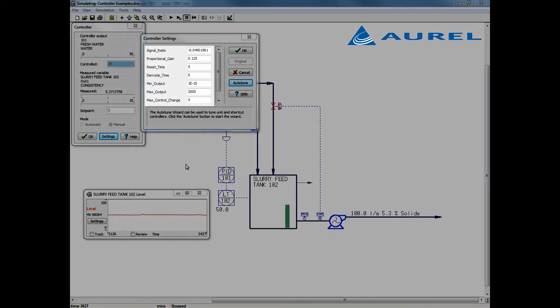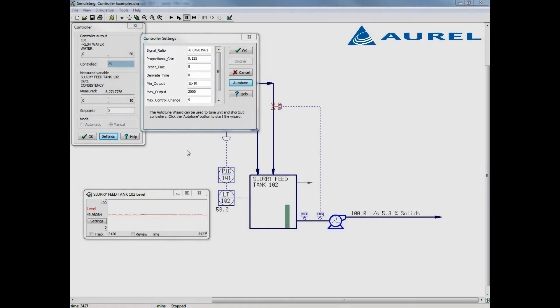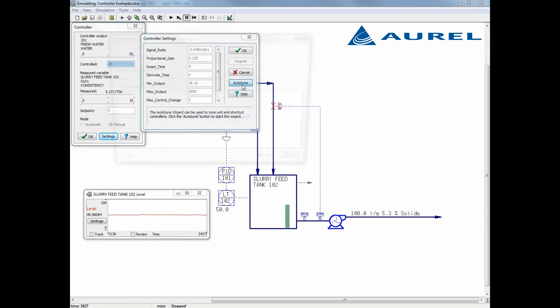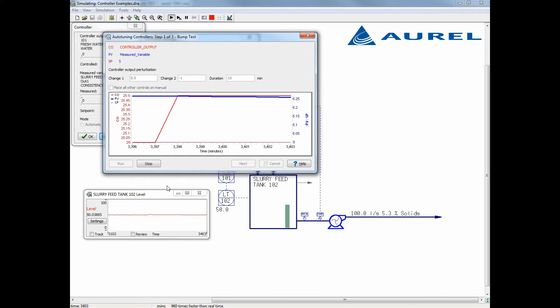One key difference from the previous formal PID controller is instead of controller gain, we have a signal ratio and a proportional gain. The signal ratio is the amount that the measured process variable will change per unit of increase in the controller output. We use these for a shortcut controller so that the controller output is immediately scaled for the manipulated variable, in this case the flow of fresh water. I will continue the same process of autotuning the controller here, by running the bump test.